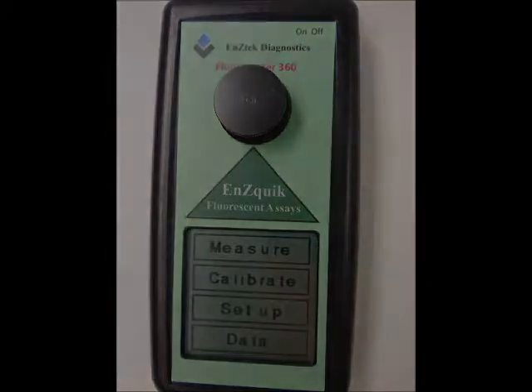The testing performed in this video will not contain any incubation steps and is intended for situations where the user does not need to detect low levels of bacteria. The rule of thumb is, if you need to detect less than 1,000 CFU, then follow the normal instructions which contain the incubation steps. The normal incubation time required for the EnZtek assays is only a short additional 5 hours.